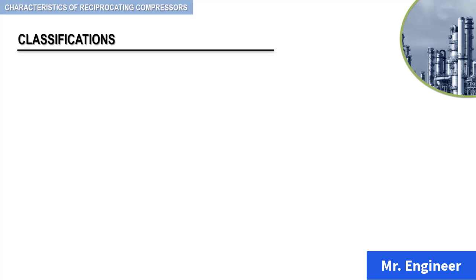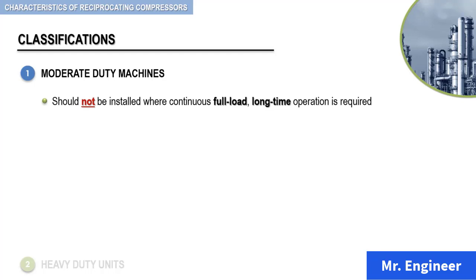Manufacturers design reciprocating compressors to match the exact need of the user. These compressors fall into two general groups: moderate-duty machines and heavy-duty machines. Moderate-duty compressors are designed for reliable operation over a reasonable service life, but should not be installed where continuous full load long-time operation is required. This does not mean that these units will not operate for long full load periods. It does only mean that maintenance costs will be greater than normal.